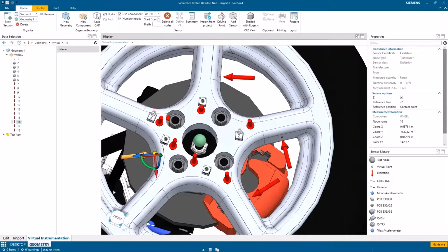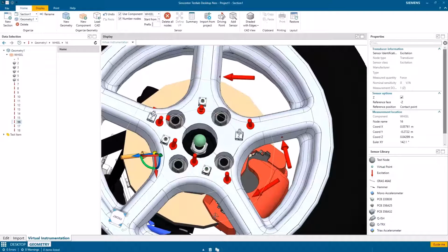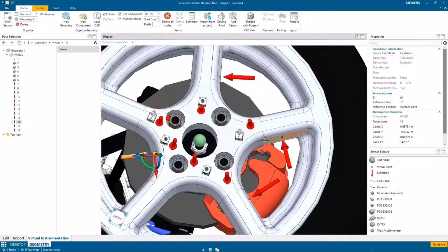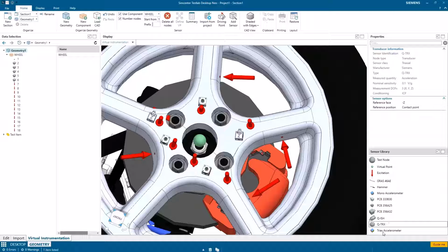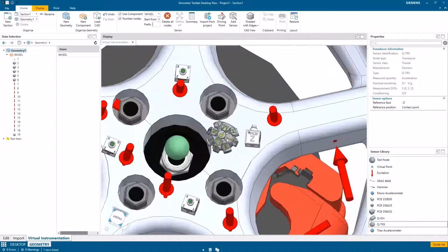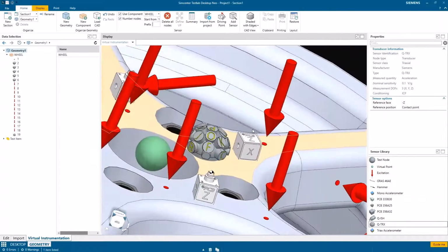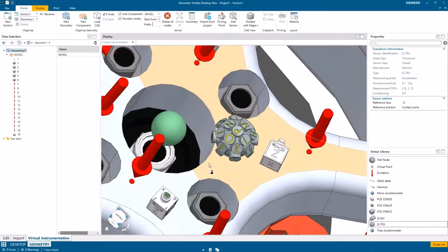So now I've got some impacts. I've got a couple of different directions. In the case of using one of our integral shakers, we even have these components like the QTRX, which is the sort of multi-plane, in-plane adapter. And so you see we've got this sort of shell device with several different mounting positions on it.